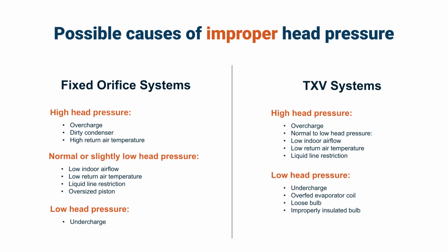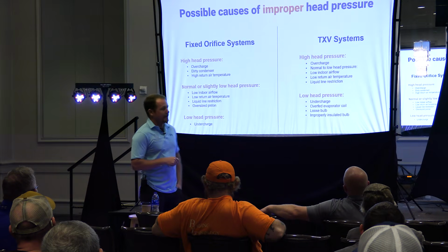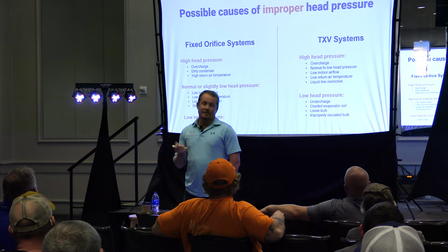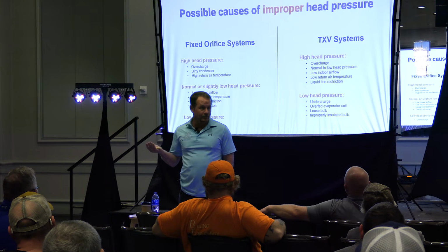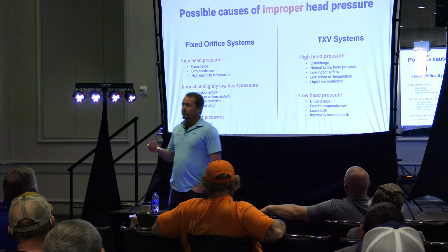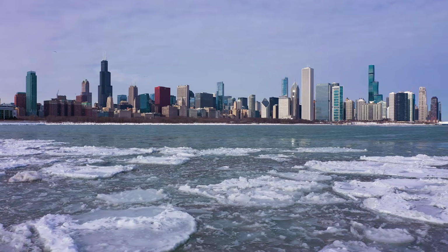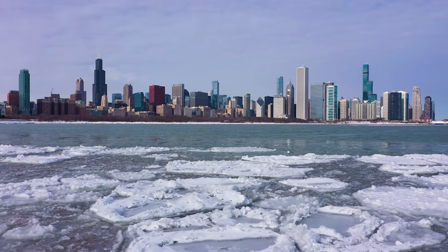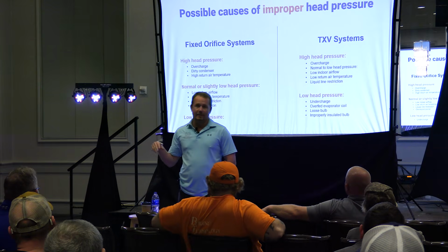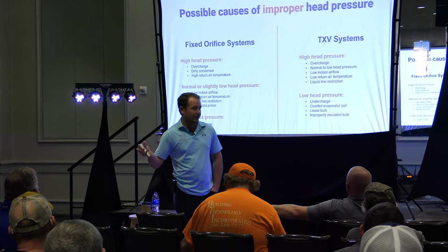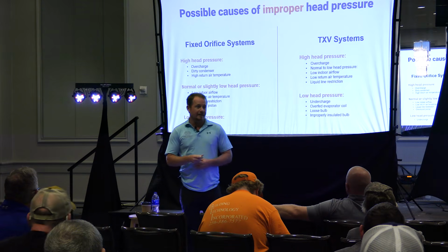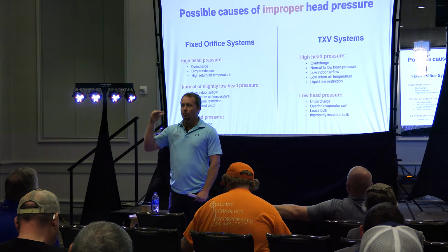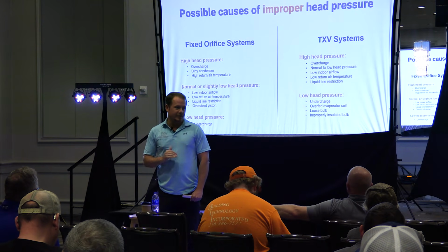Possible causes of improper head pressure. That's another key one. Is it possible to have head pressure that is too low? Depends on what you mean by it, but sure, it is possible. A perfect example is a couple years ago there were cold snaps that went through Chicago, and all the market refrigeration guys had absolute nightmares because outdoor temperatures were -30, -40 degrees. The outdoor temperature was significantly lower than what you want your lowest box temperature to be inside the store.